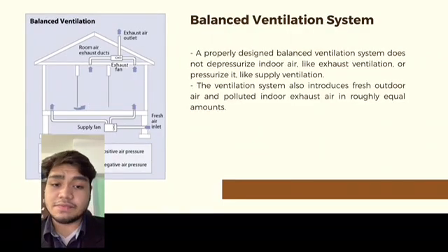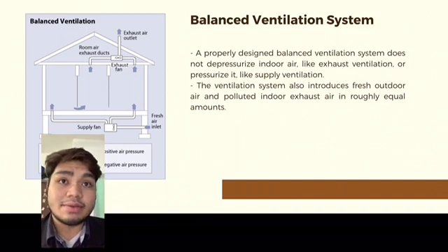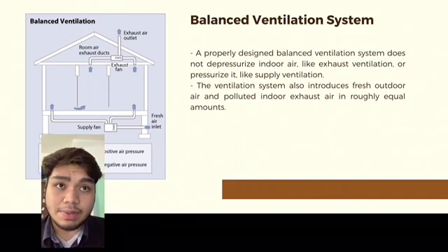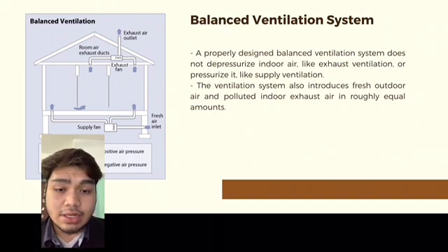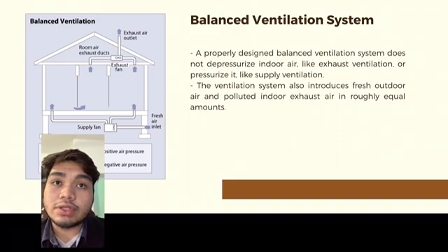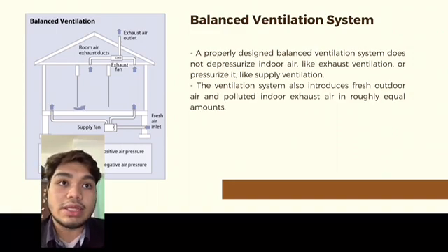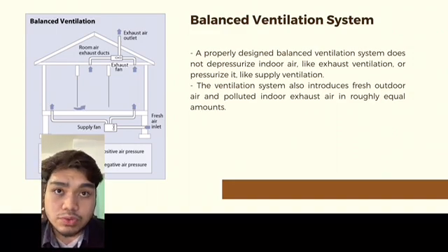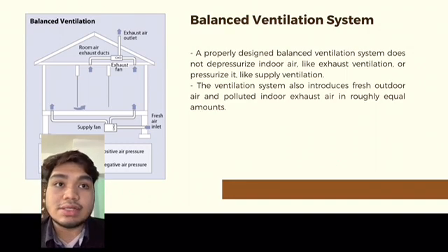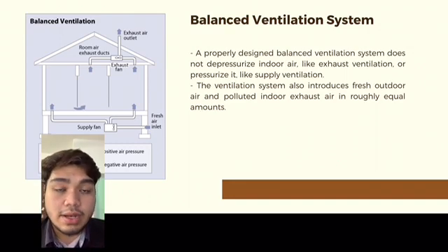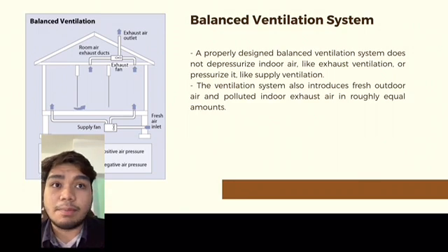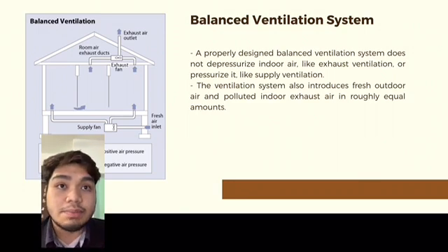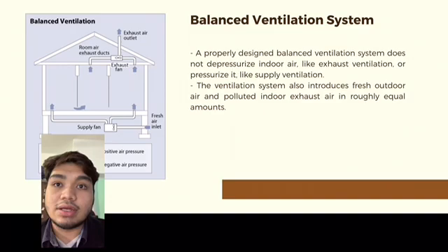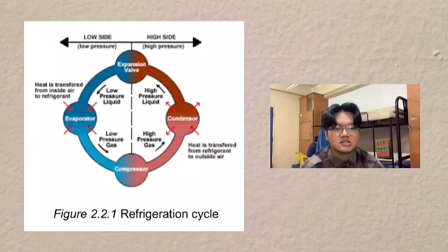The last one is the balanced ventilation system. A properly designed balanced ventilation system does not depressurize indoor air like exhaust ventilation or pressurize it like supply ventilation. The ventilation system also introduces fresh outdoor air and polluted indoor exhaust air in roughly equal amounts. The system often uses two duct systems and two fans to do its job well. If the supply and exhaust vents are positioned in appropriate positions, the balanced ventilation system facilitates the correct distribution of clean air.